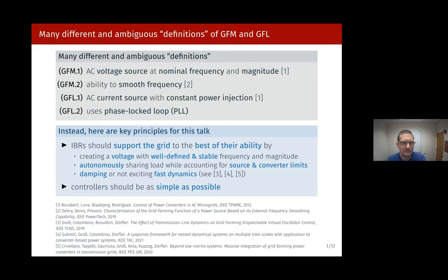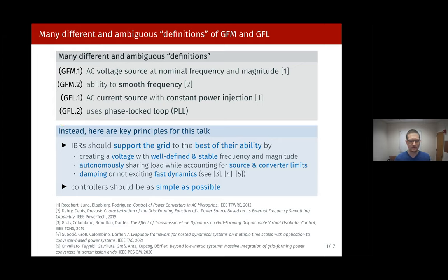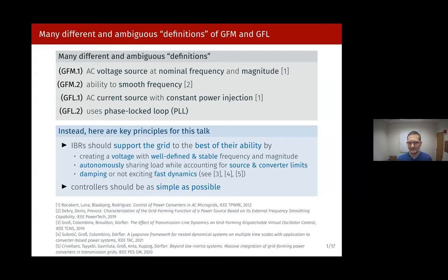To sidestep that issue, I would propose a slightly different perspective, similar to what Deepak Divan was discussing last week. Instead of asking whether something is grid forming or grid following, we should set principles for what we want from inverter-based resources. First, they should support the grid by creating a voltage with a well-defined, stable frequency and magnitude. They should autonomously share load while accounting for source and converter limits. And they should dampen or at least not excite fast dynamics.